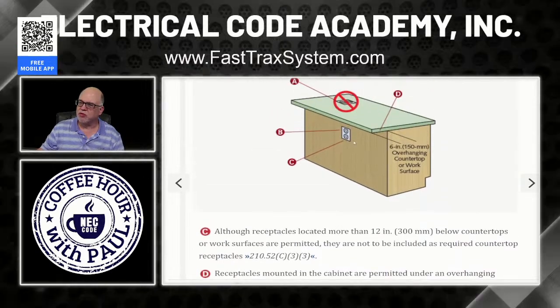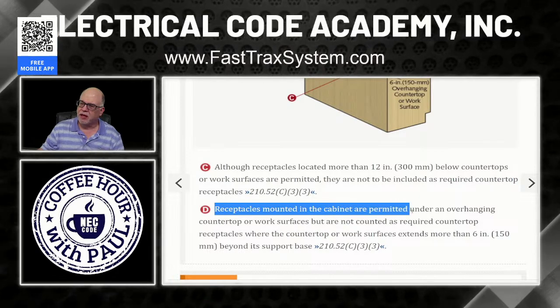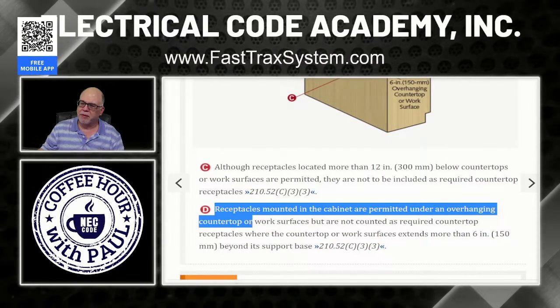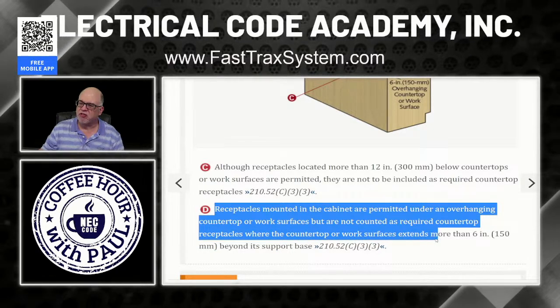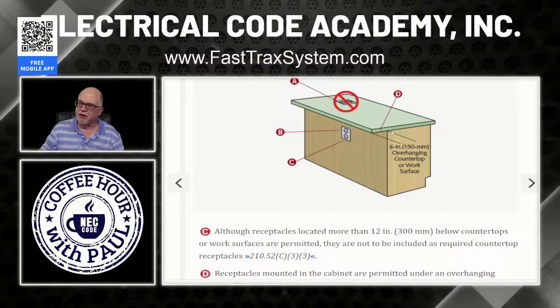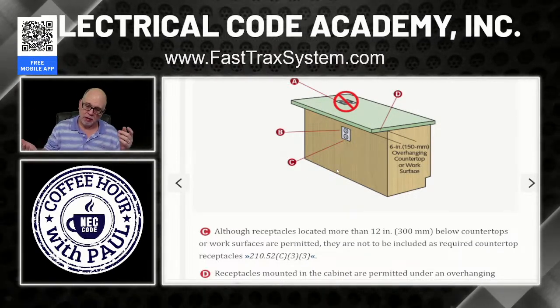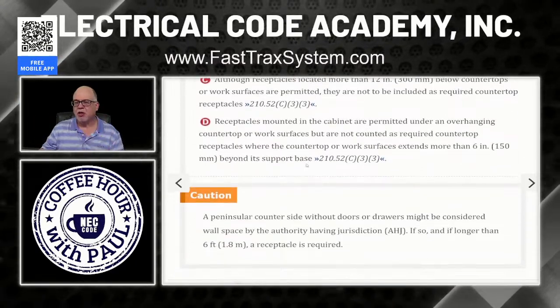Now again, this receptacle, we'll talk about D right here. Here's the overhang. Receptacles mounted in the cabinet are permitted under the overhang of a countertop or work surface, but are not counted as required countertop receptacles where the countertop or work surface extends more than 6 inches beyond its support base. Okay, so this is the support base and this is the edge of the countertop. If this measurement right here is more than 6 inches, then I could not put a receptacle under here to serve the countertop. But that does not mean that I could not have a wall space receptacle. That would be okay as well if that was a wall. Okay, just kind of wanted to throw all those things out there.